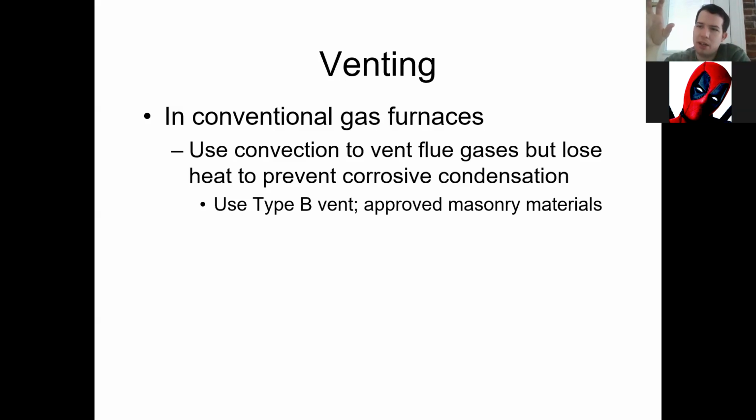What happens every time that it leaks flue gases out of the venting is the flue gases decrease in temperature. And as they decrease in temperature, that's when you're going to have condensation, which is going to eat through that metal. It's going to eat through that flue piping and that ventilation. It literally destroys it.